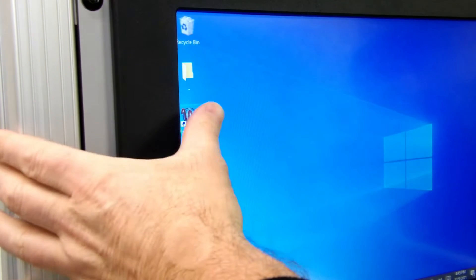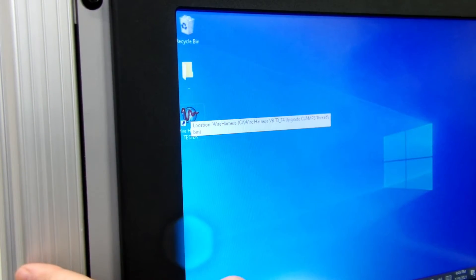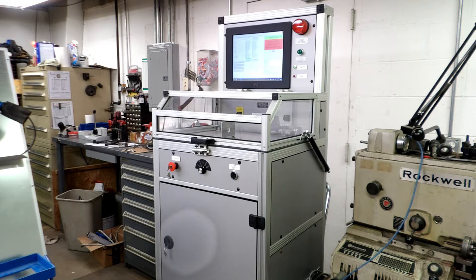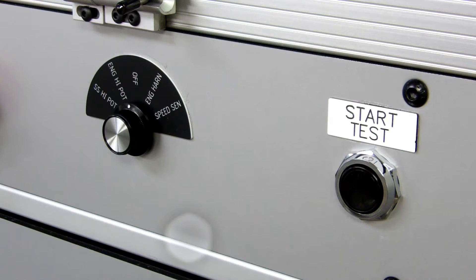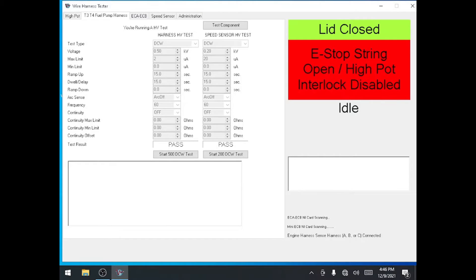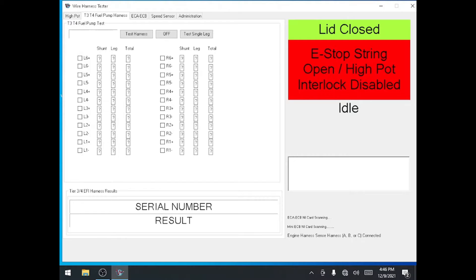At the operator console, if the test software is not already open, double tap the wire harness tester icon on the desktop. Below the lid on the console, change the selector switch to ENG HARN. The software will change to the engine harness test screen.